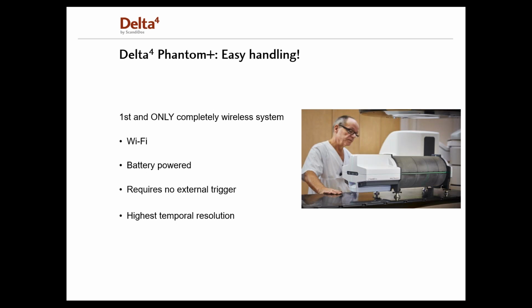The Delta4 Phantom Plus also offers easy handling. And this is because the system is completely wireless. The communication to the PC is done through Wi-Fi, so no communication cable is needed. The system is battery operated and therefore no power cable is needed either. The capacity of the battery is more than 4 hours, but if you would run out of battery, then you can just charge it while using the Phantom. And with electrometer technology that is much faster, the detection of the dose pulse from the accelerator can now be done by the internal electronics, which eliminates the trigger cable. However, we still measure pulse by pulse, which is the most accurate and the only way to ensure that individual control point doses can be measured.